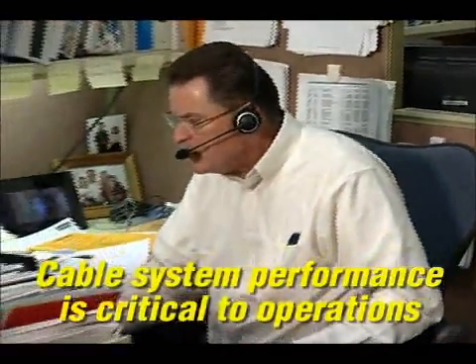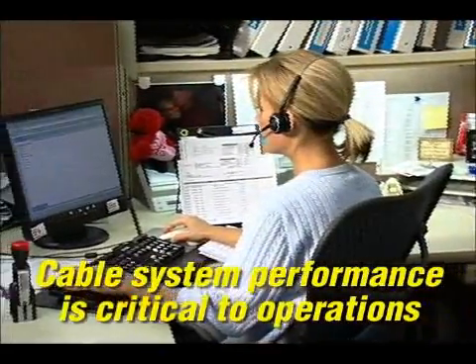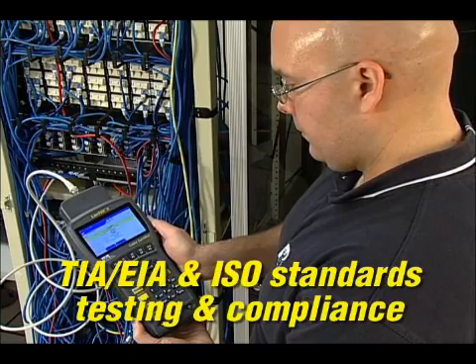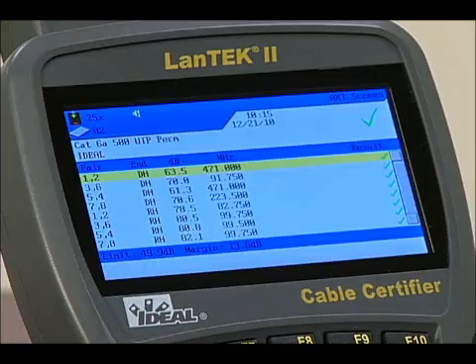Voice, video, and data are converging on a single network, making cable system quality critical in schools, hospitals, industry, and businesses. Categories or classes designate differences in unshielded twisted pair, screened twisted pair, and shielded twisted pair cables — the most common designation being the maximum frequency supported per pair. Cable certifiers like the LanTEK II perform tests required by TIA, EIA, and ISO standards to certify these cable categories.